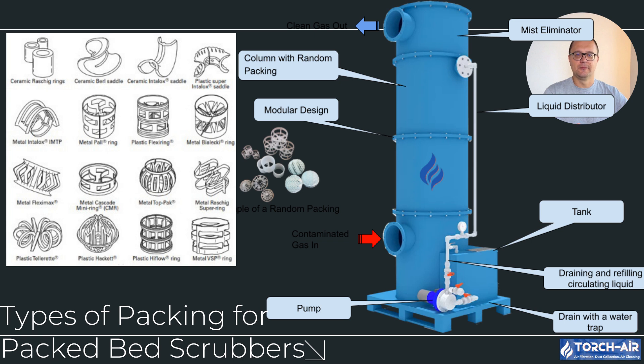Pall rings: these are an upgrade from Raschig rings, designed with more open structures to improve gas and liquid flow. They provide a higher surface area while keeping the pressure drop low — that's why they're so popular. They offer better efficiency without adding too much resistance, and are made from polypropylene, metal, or ceramic, so they can handle a variety of industrial conditions.